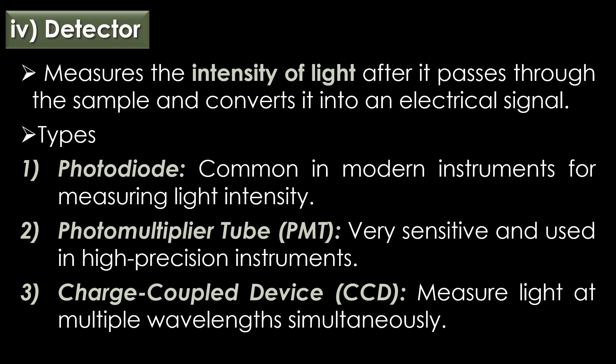Detector: the detector measures the intensity of light after it passes through the sample and converts it into an electrical signal. Three types of detectors are used: photodiode, photomultiplier tube, and charge-coupled device. The photodiode detector is common in modern instruments for measuring light intensity. The photomultiplier tube is very sensitive and used in high-precision instruments. The charge-coupled device can measure light at multiple wavelengths simultaneously.